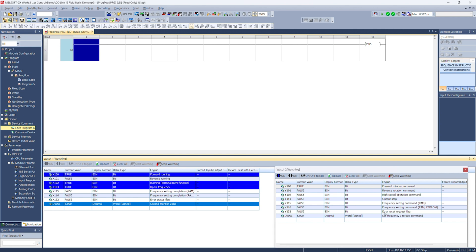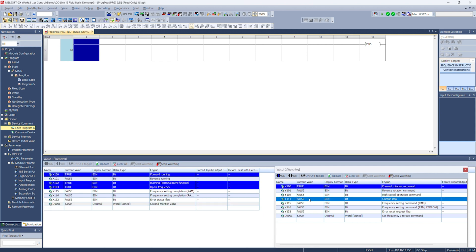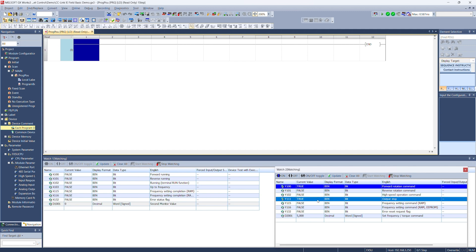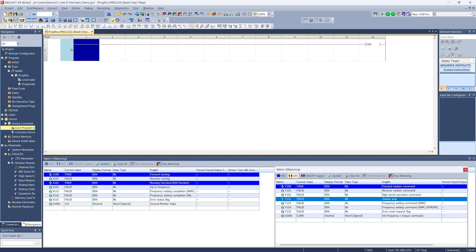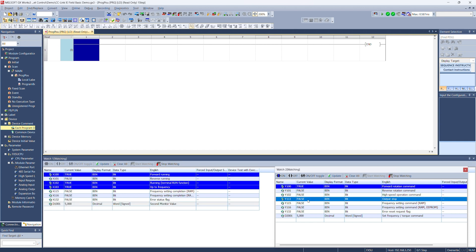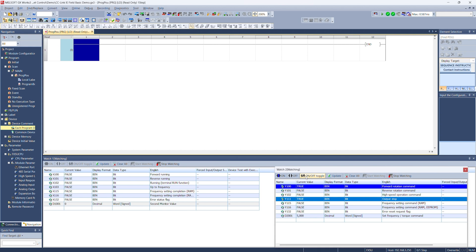And lastly, we'll take a look at output stop. We've seen this speed go smoothly from 0 to 6,000 or 0 to 5,000 and smoothly back down with gradual acceleration and deceleration. If we turn on the output stop flag, we should see this cut off immediately back to 0. There we go. Immediately back to 0. Not running anymore. If we turn off output stop, it will not immediately jump back to 5,000. We'll have to regain our speed and it'll accelerate smoothly. So this would be good for kind of an emergency stop situation. Let's try it again. We'll toggle it on and you'll see your speed drop immediately, output cutoff.